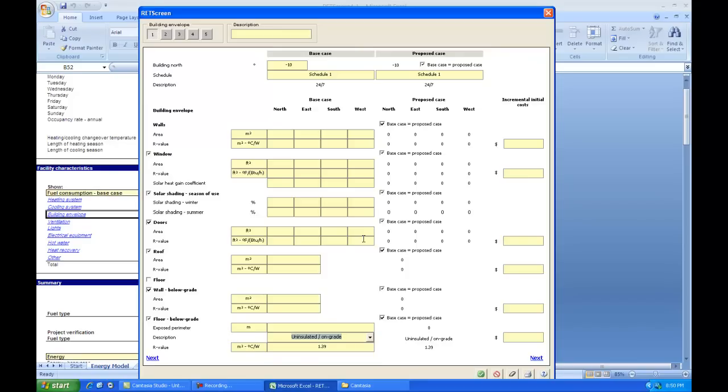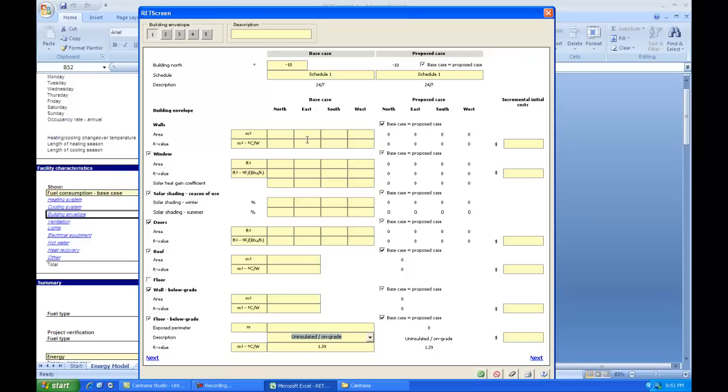So that's the basics of what you're going to find inside the building envelope. The other thing I want to mention right now in terms of laying out your buttons, best to do the windows near the end. The windows are going to be cut out of this wall here. So whatever you model as a wall on the button you're at, in our case number one, the windows that we model on button number one, RETScreen is going to assume that those windows exist in this wall here. So if this is an above grade wood frame wall, for instance, then we'd want to put all the windows associated with that type of wall here, because it's going to reduce the area of the wall as it adds in the windows.